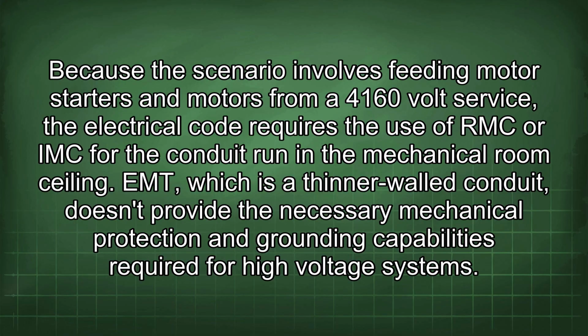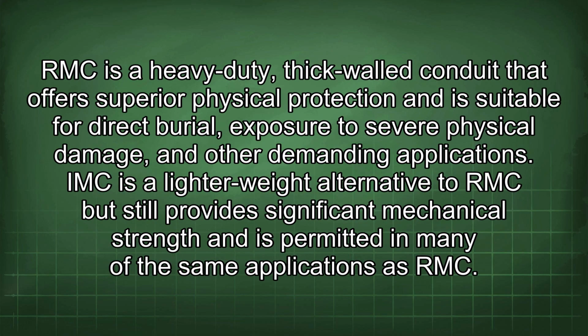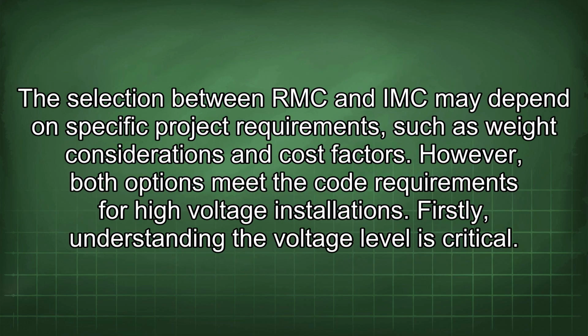EMT, which is a thinner-walled conduit, doesn't provide the necessary mechanical protection and grounding capabilities required for high-voltage systems. RMC is a heavy-duty, thick-walled conduit that offers superior physical protection and is suitable for direct burial, exposure to severe physical damage, and other demanding applications. IMC is a lighter-weight alternative to RMC but still provides significant mechanical strength and is permitted in many of the same applications as RMC. The selection between RMC and IMC may depend on specific project requirements such as weight considerations and cost factors. However, both options meet the code requirements for high-voltage installations.